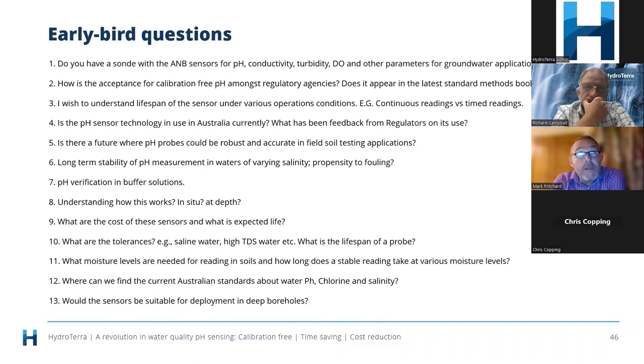We can extend that, just to give you some background. We have 18 pellets within the front of the transducer, and we go around those pellets, charging them at different time intervals to get the pH readings. Now if we reduce the pellets we're reading—instead of reading all 18, reading just 3 in each section—that will extend the lifespan of the transducer, but it will affect our accuracy. For some applications, like in concrete, they're not really concerned over the accuracy; it's a yes-no question they're looking at. So by reducing the number of pellets we manage, we increase our lifespan but decrease our accuracy.